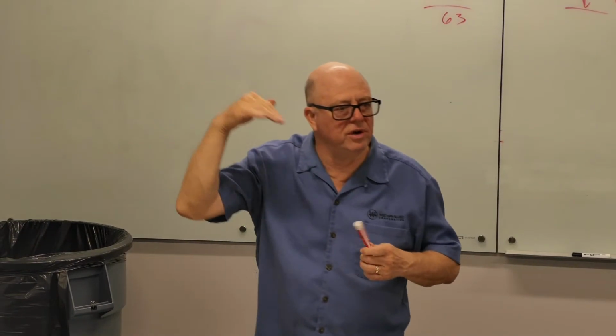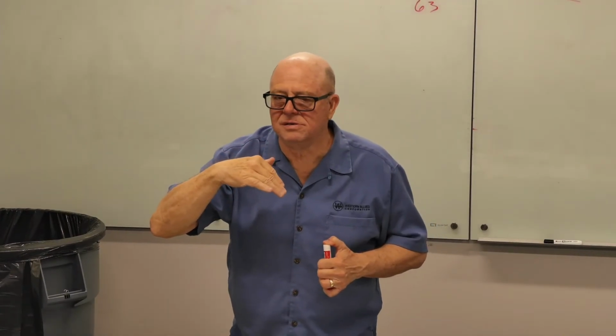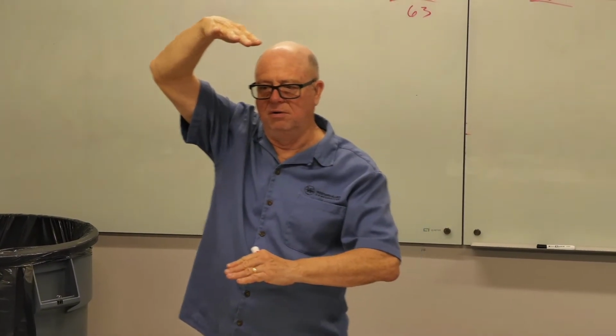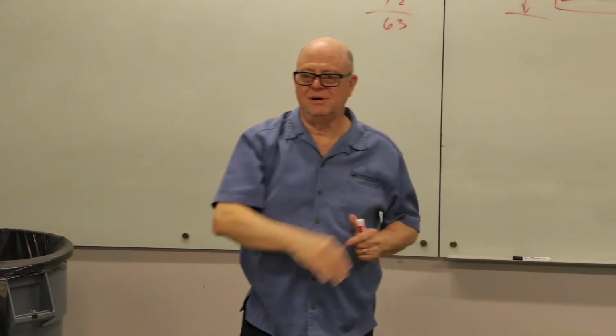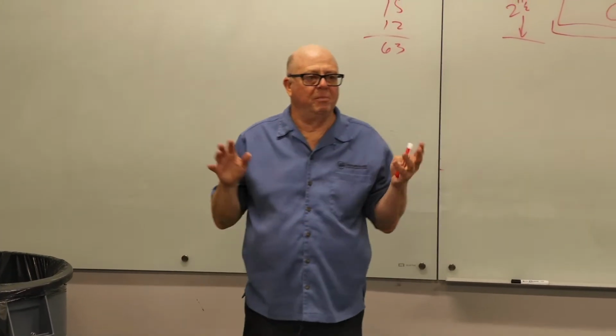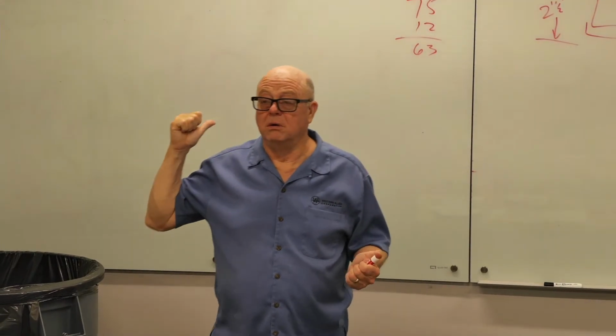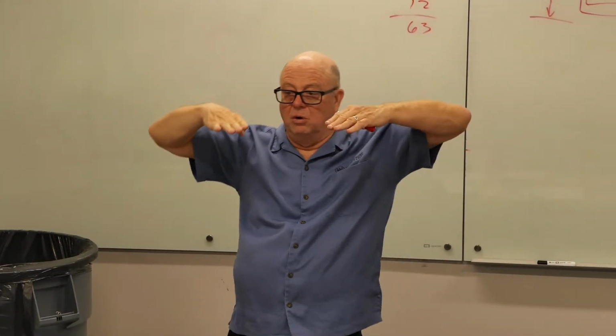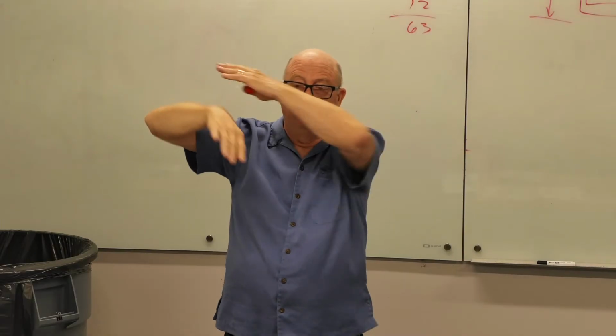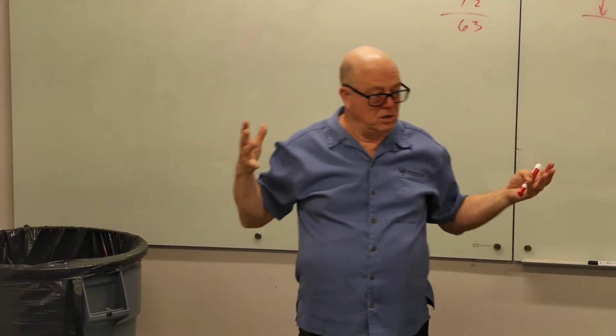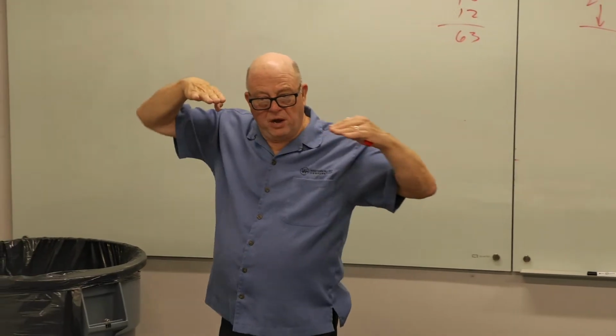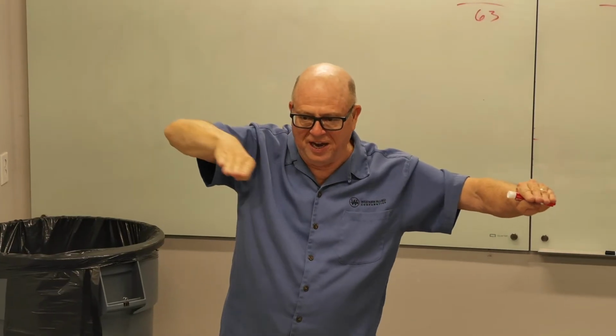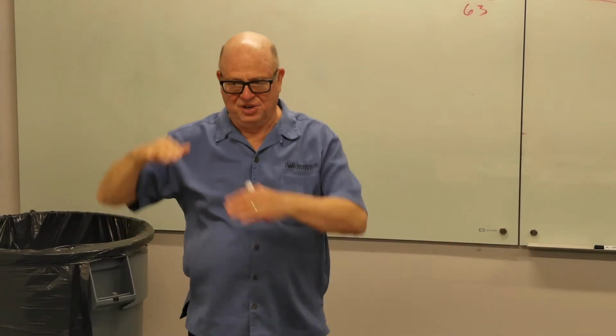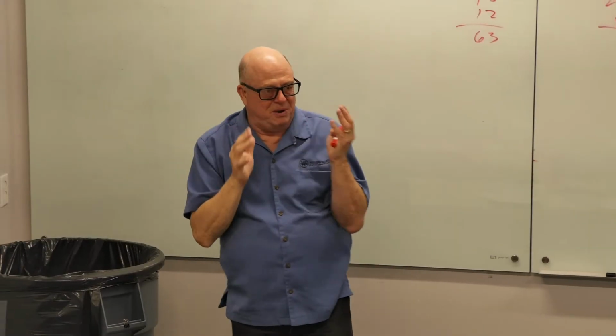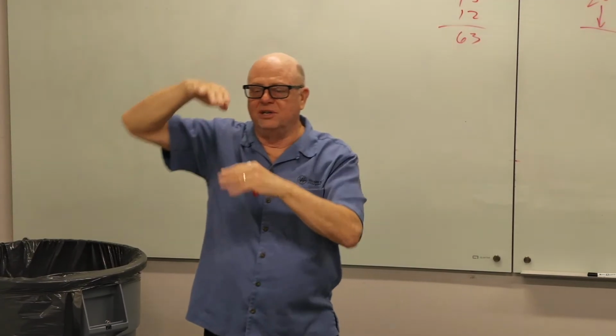So your condensate drain, how much height do you think you need for the condensate to flow? I don't remember the plumbing thing. It's specified in the code. You've got to have so many inches of fall in so many inches to meet code. And if you scrape it down at the very minimum like that, if the guy doesn't do a perfect job of putting the line in, it's going to have some dips and it won't work right. So you want to actually do a little bit better, probably, even than the code says for a condensate drain.